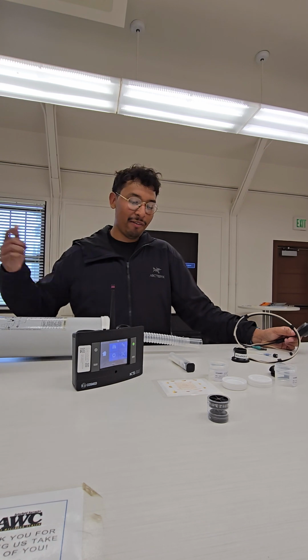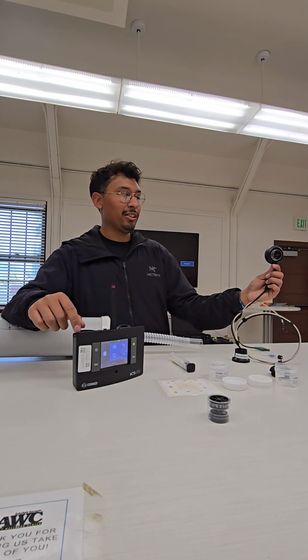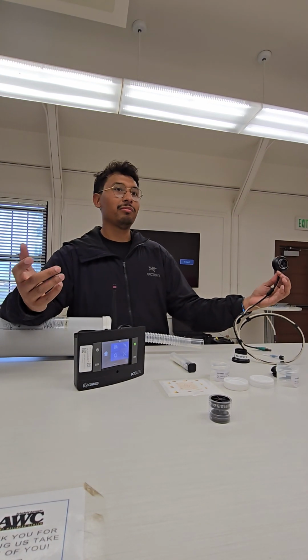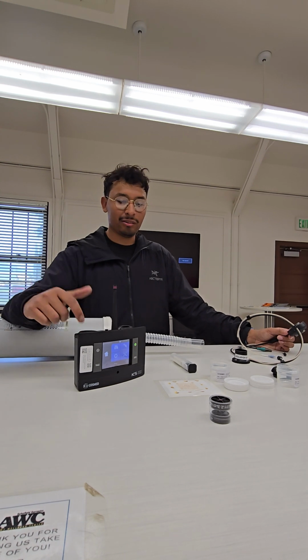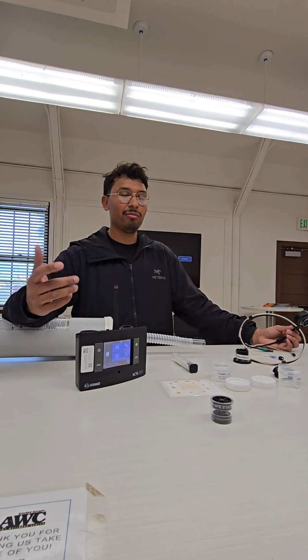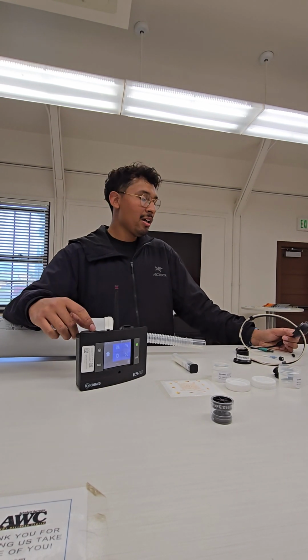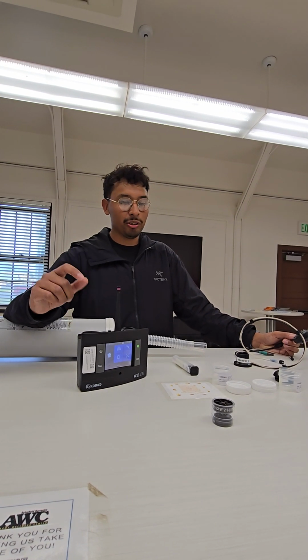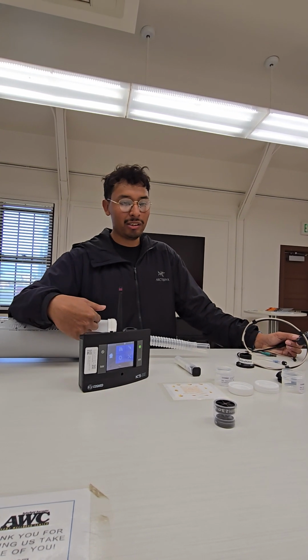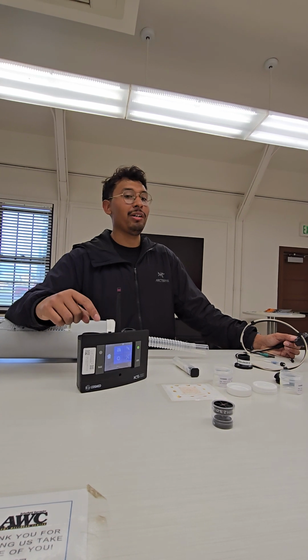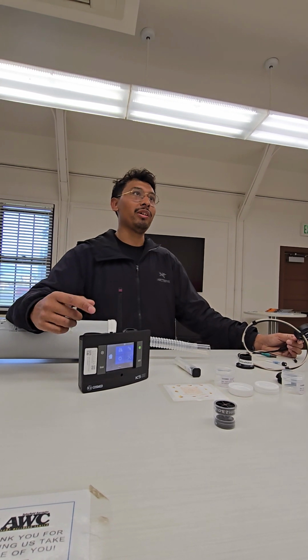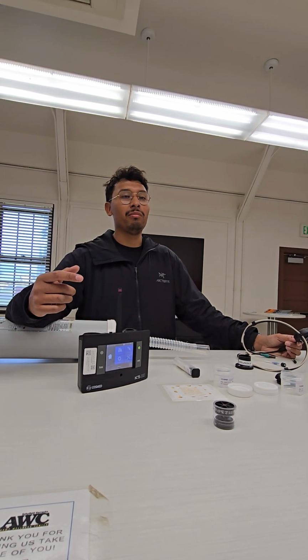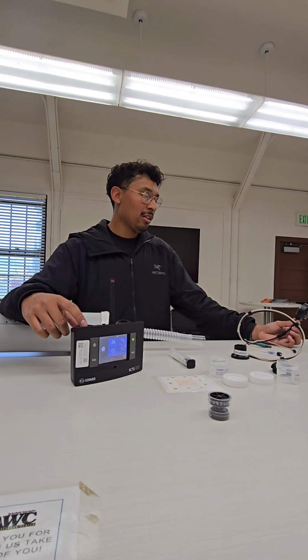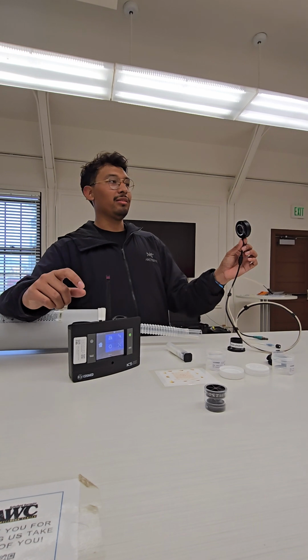But yeah, whenever you pump 3 liters through, this guy should spin roughly 100 times. So it's really just the software recognizing that it's passing or failing. You're supposed to be getting 3 liters. If you're at 2.899 or 3.1, you would be failing. So it's a pretty small error. Any questions on how this works?